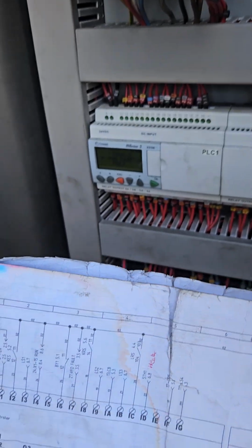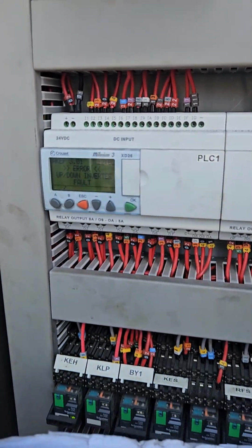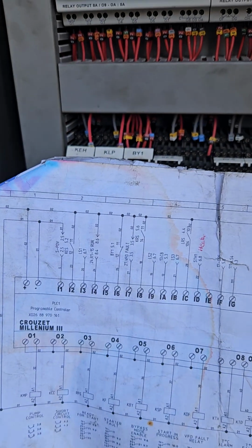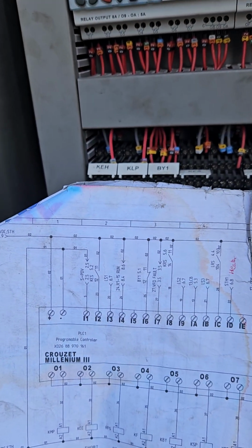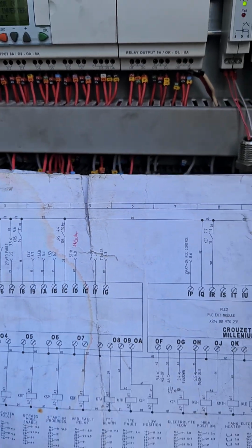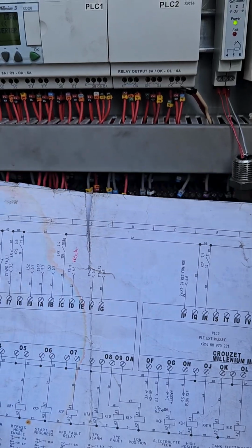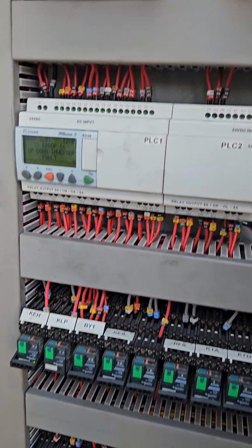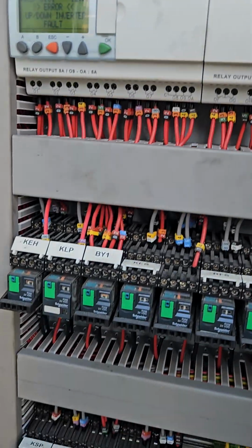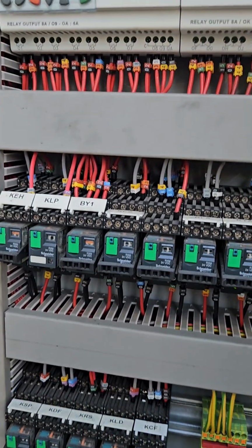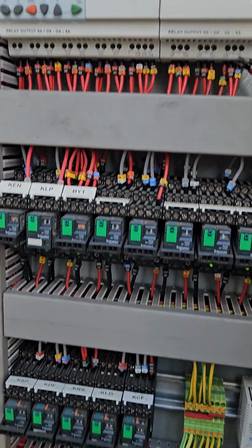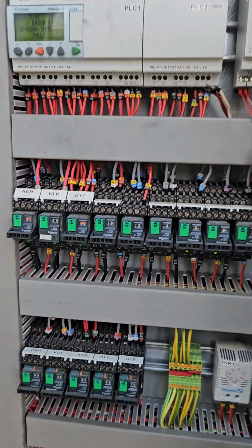Okay, as I'm about to finish up, you can see that is the PLC, and this is the wiring diagram of the PLC. It's easy if you take it one wire at a time, it makes sense. And yeah, at the bottom we do have relays. Someone will ask, why do we still use relays if the PLC is doing the logic? Relays can switch higher currents, so it will happen that the load that is connected to this PLC is carrying a higher current, so you need the relay to do the switching.